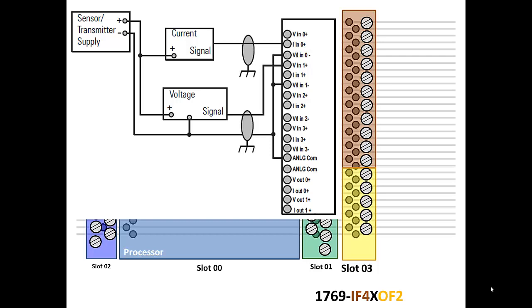In our little wiring diagram, there illustrates both the connections for a current and a voltage application. In the field, 4 to 20 milliamps is the most practical because zero is invalid, so if you have an open conductor in your input circuit, you'll get zero milliamps and the system immediately knows that that's not valid. The top part shows how to connect up a current signal and then right below it voltage signal. We're going to do voltage signals.